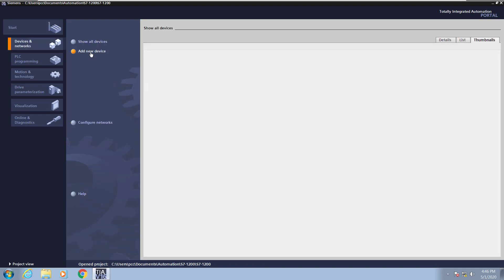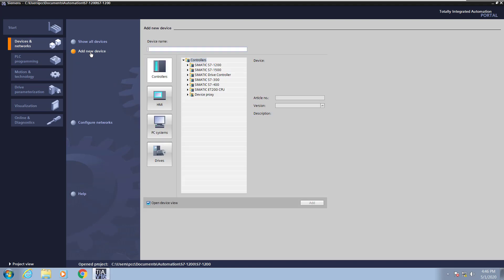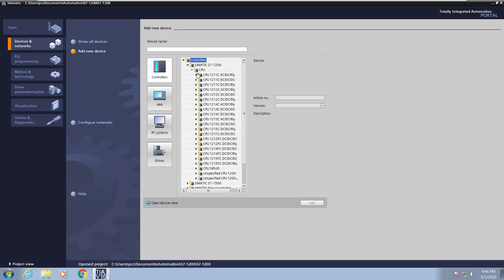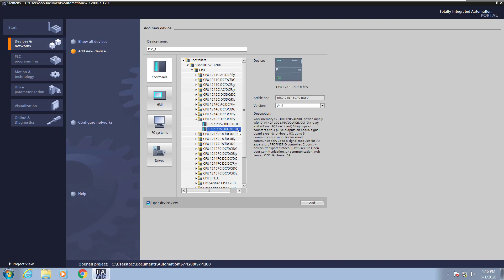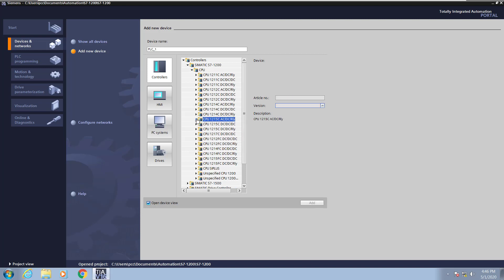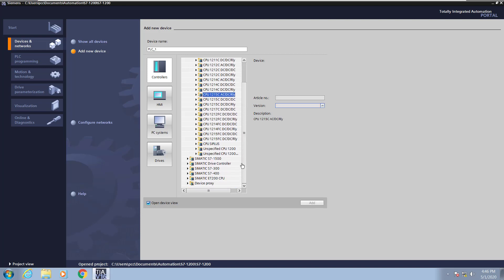I will select add new device and then select the controllers category. Then I will expand out all the S7-1200 CPUs and you can pick the different category of CPU that you would like. I'm going to pick a 1215 CPU and then select a specific part number. Here I can select the version of the firmware but what I'm going to do is actually do an unspecified CPU.